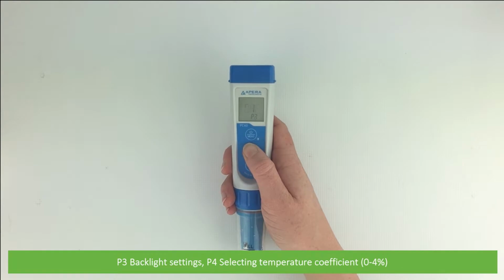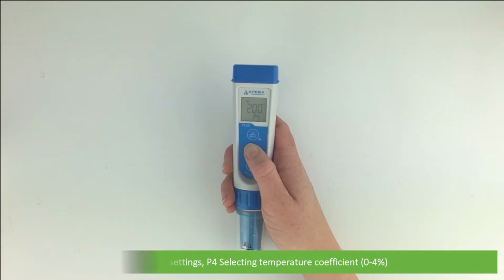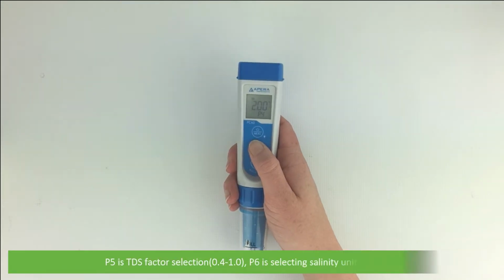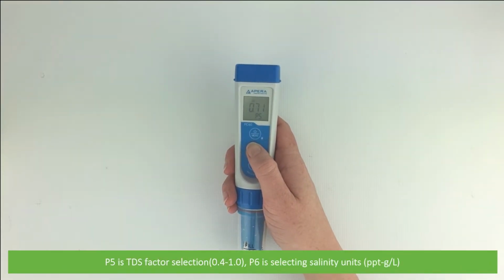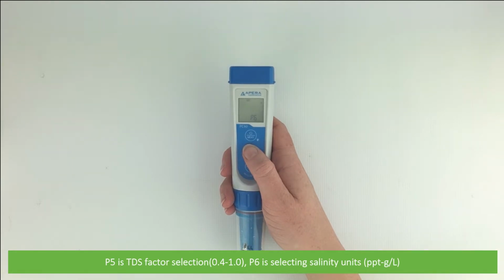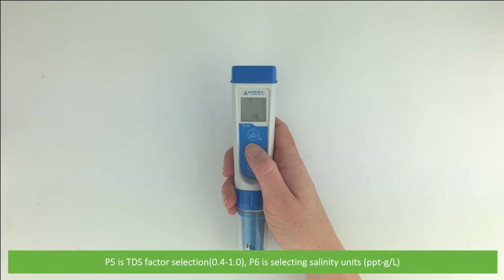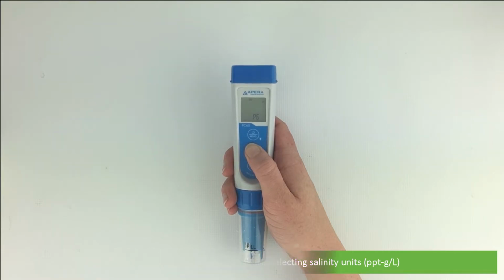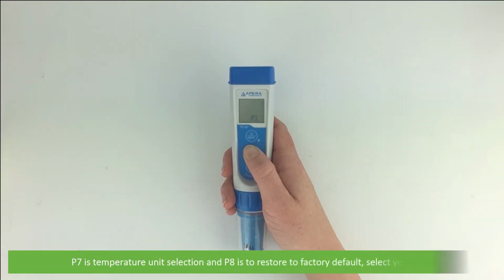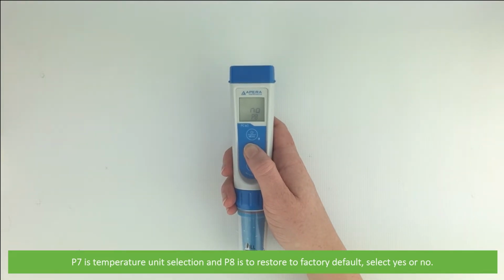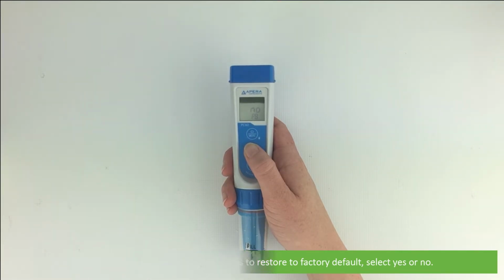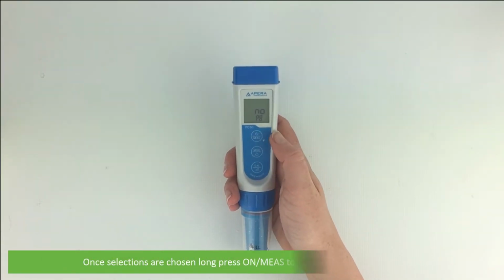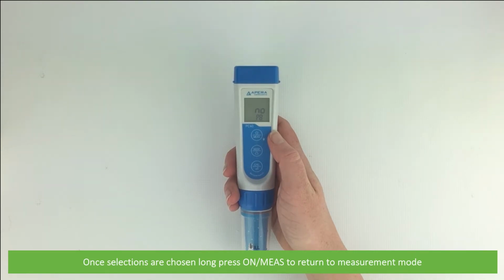P3 is backlight settings. P4 is selecting temperature coefficient, which is 0 to 4%. P5 is TDS factor selection, which is 0.4 to 1. P6 is selecting salinity units, select between parts per thousand or grams per litre. P7 is temperature unit selection, and P8 is to restore to factory default, select yes or no. Once your selections are chosen, long press on/measure to return to measurement mode.